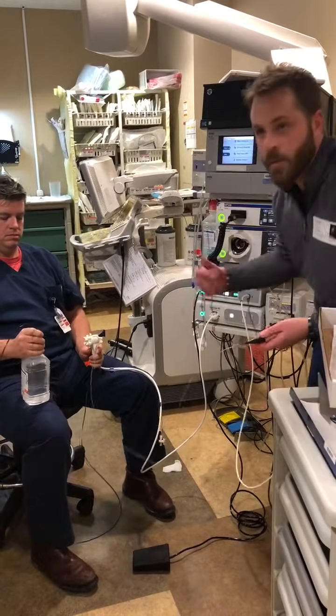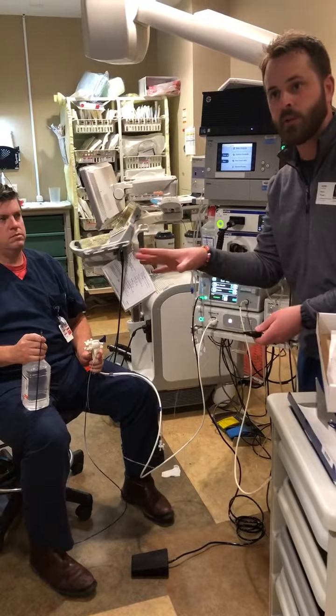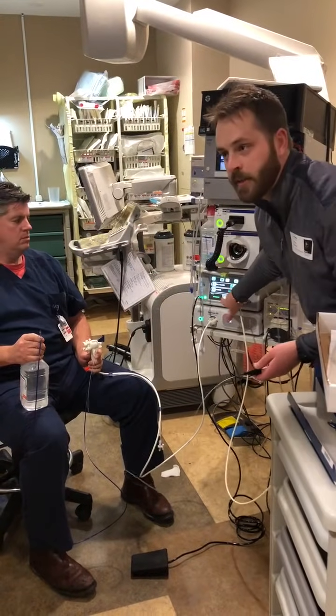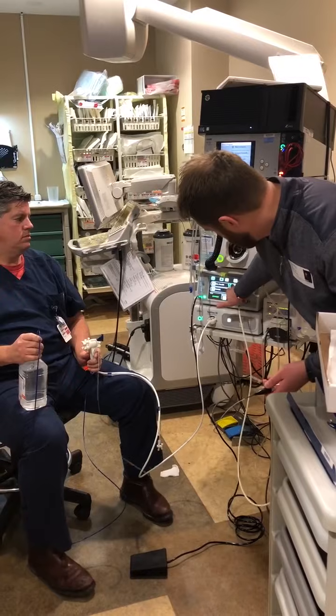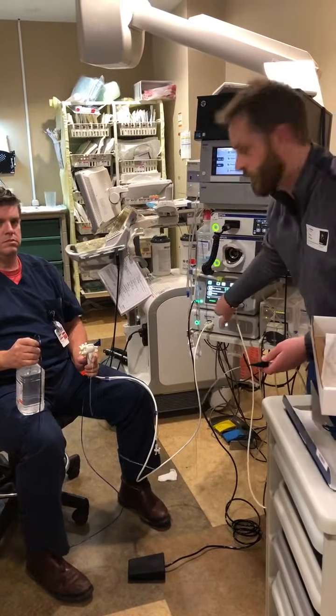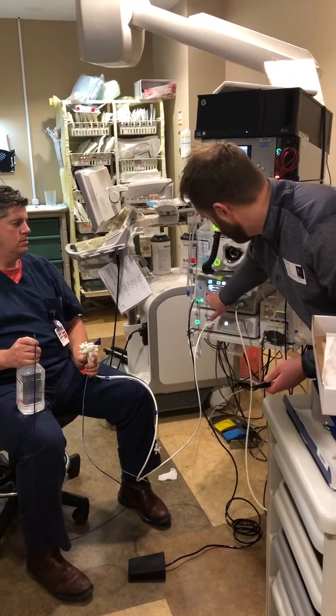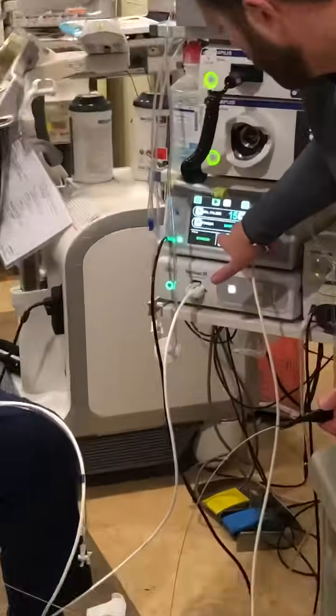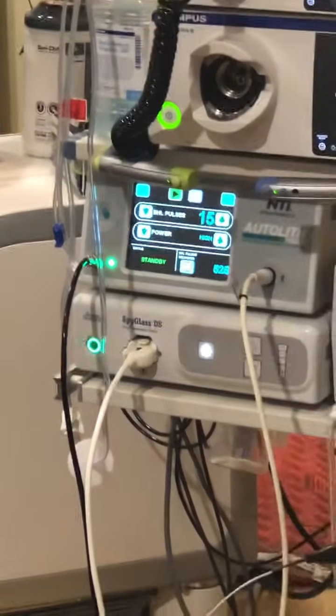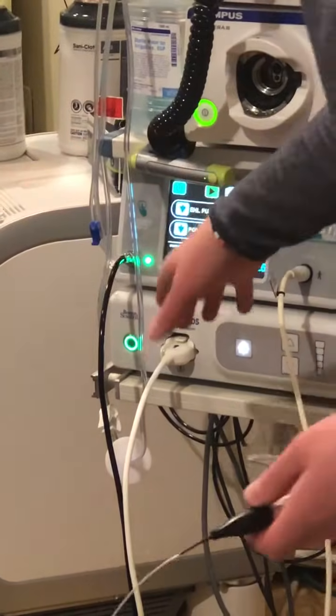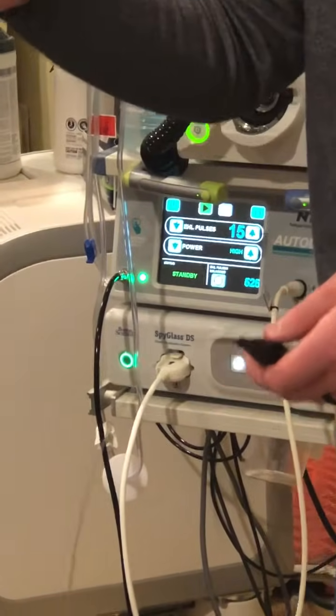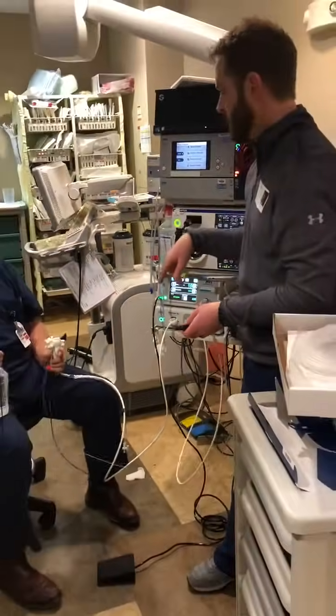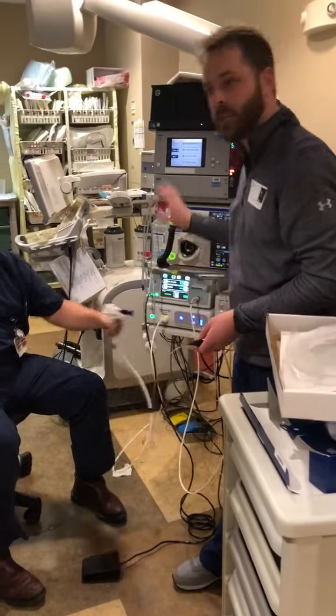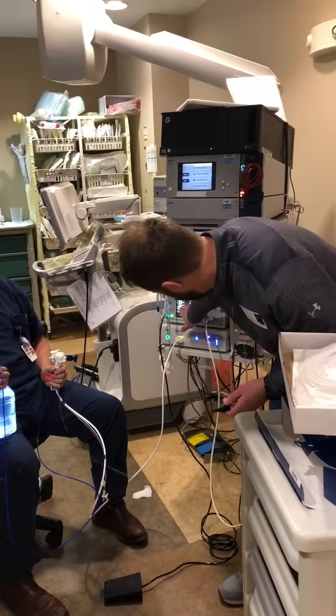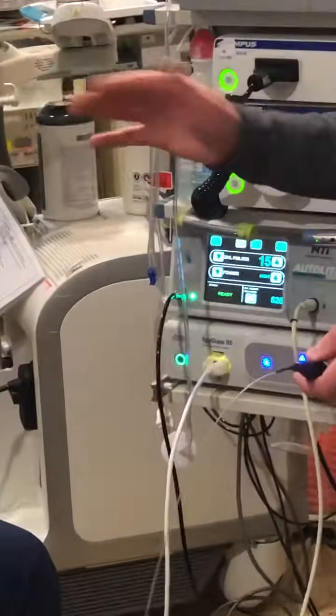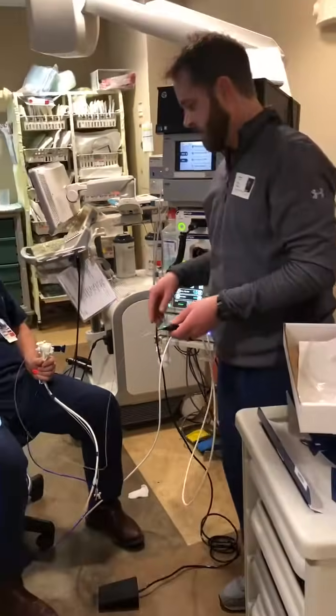Then on your screen, you have a couple options. You have how many pulses, so how many times it's going to shoot each time you activate it, and then your power settings. My suggestion is you always start at 15 pulses and always start on high. So you have low, medium, or high. Once it's connected, once the doctor says, okay, I'm looking at the stone, I'm where I want to be, I'm ready to start using it, it's kind of just like safety settings on any other thing, you have to hit play. Once you hit play, it's active and ready to use.